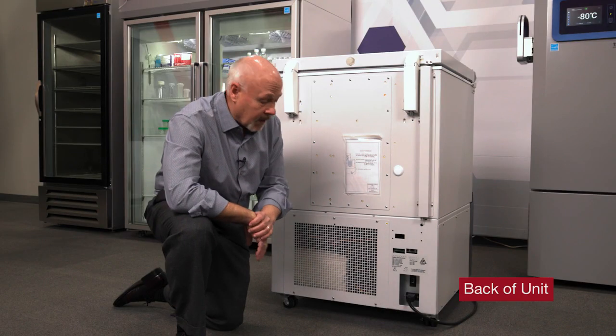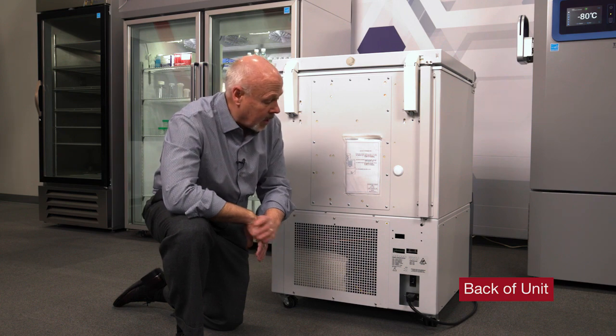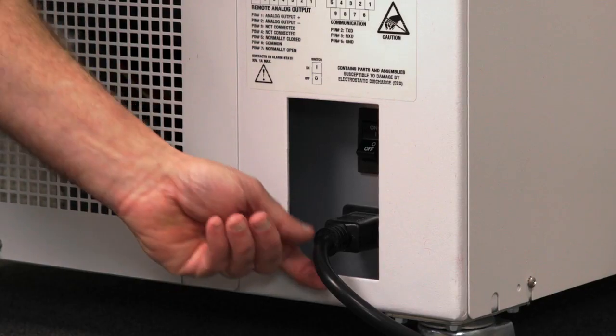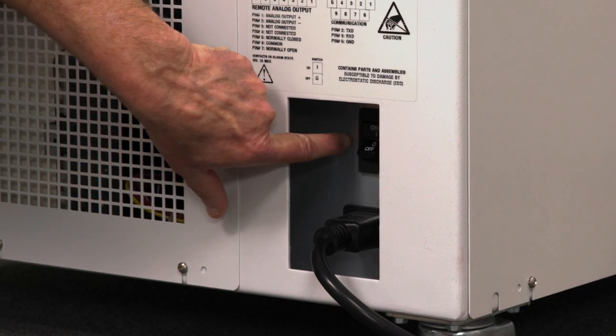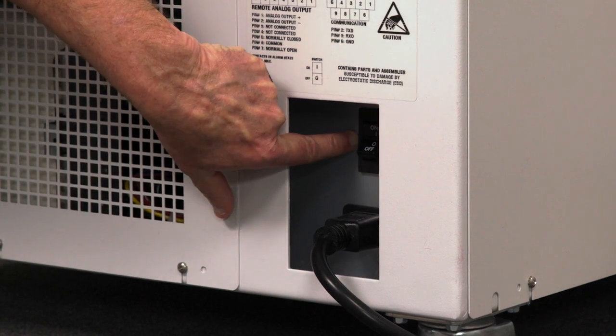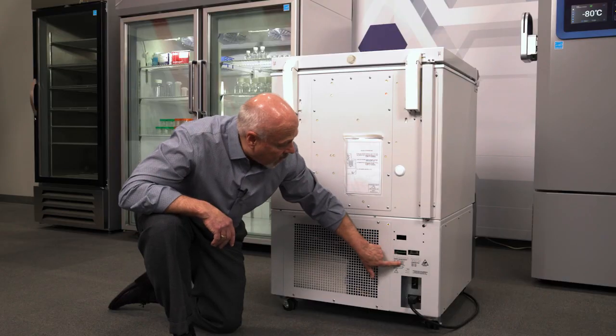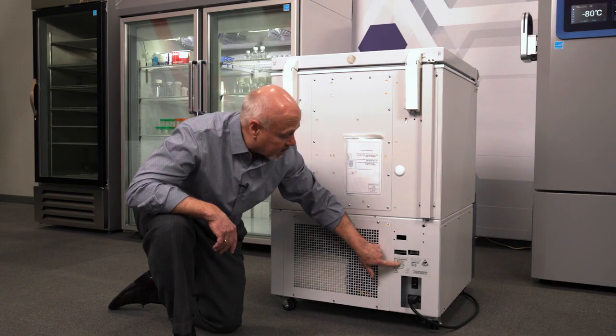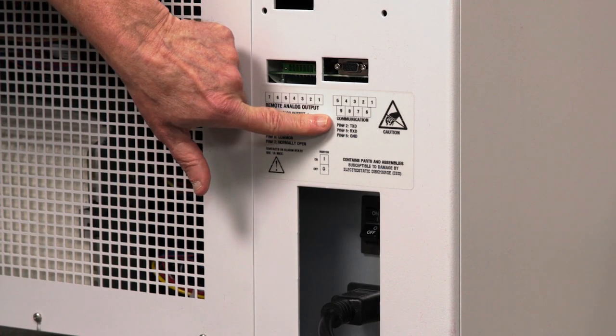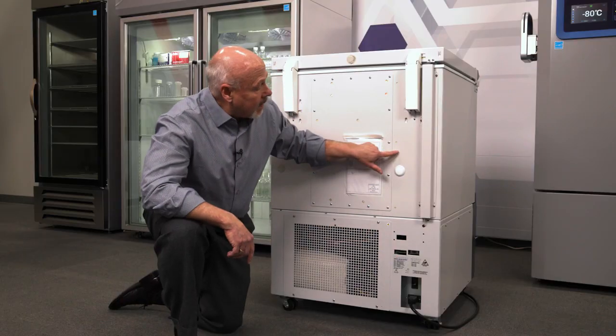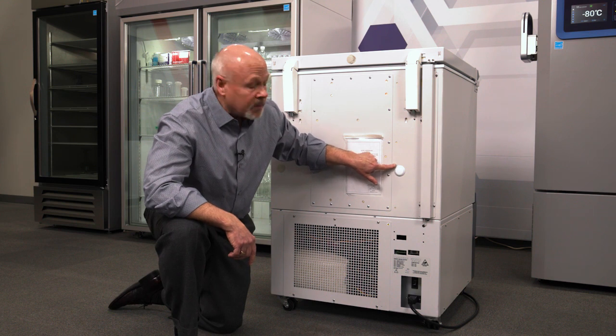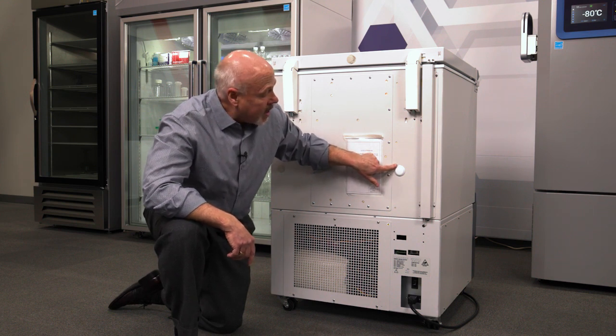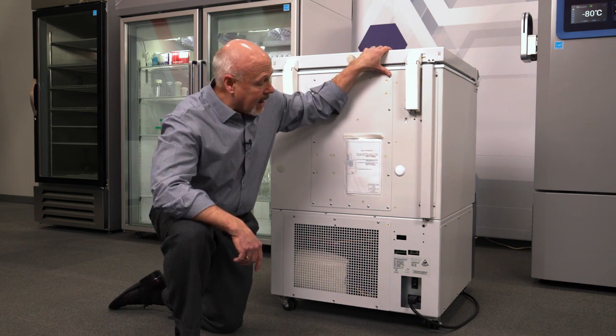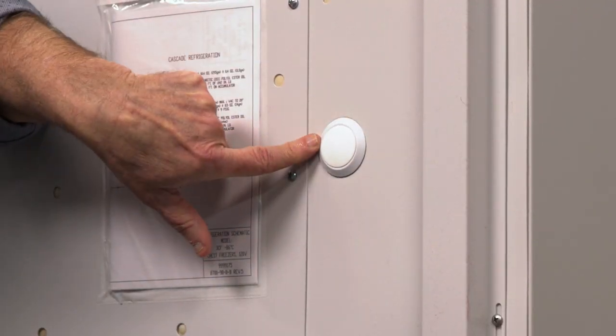Okay, there are a couple of key things that I want to point out on the back of the unit. The first is where it plugs in, which is right here. You can see the plug-in. Your on-off switch, toggle switch, is here. We have 2 monitoring devices for house systems, an RS-485 and a 4 to 20 milliamp. And then the access port for the back, this would be for a remote monitoring system. Instead of going through the lid and through the gaskets, you want to go through this insulated port in the back.